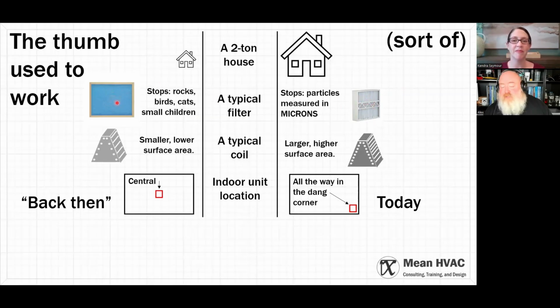This is what systems always used to look like back when we were using that rule of thumb. The coils we used were smaller, and the spaces between the rows of fins were wider, so air had an easier time getting through your old system's coil. The newer system has more resistance because it's a larger, tighter surface. So just by swapping out the unit, if you didn't change the blower, you could swap the outdoor unit and coil and leave the furnace, and you'd probably end up with less airflow because that coil is more restrictive than it was.